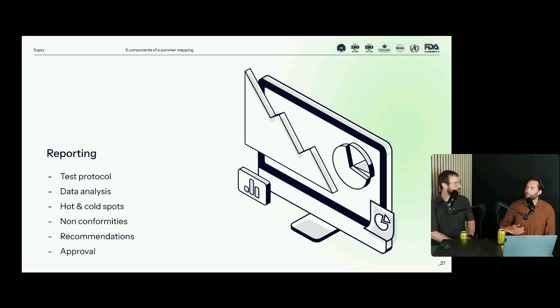What does a box plot exactly represent? A box plot really represents where you have the median or mean of temperatures, depending on what you choose, so the average, and then where 50% of all your measurements lie, and where 95% of all your measurements lie. It really gives the best picture of the typical temperatures to expect in each position.